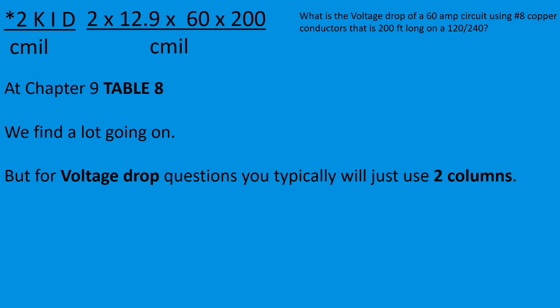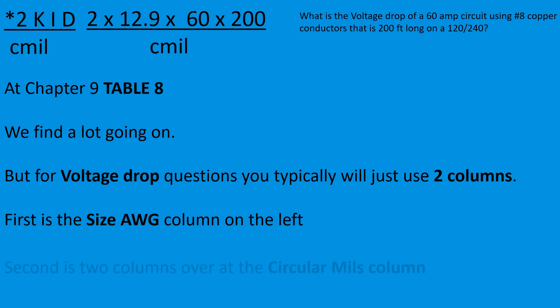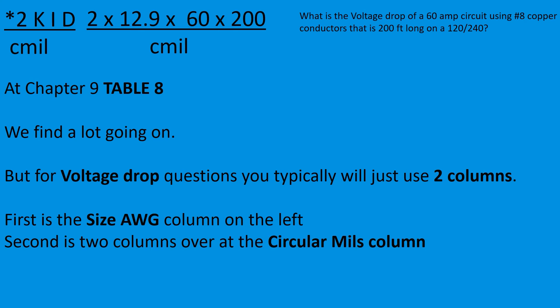For voltage drop questions you typically just use two different columns. The first one is the size AWG column on the left. That's going to be your size wire. So first select your size wire. We're using a number 8 copper. Second is two columns over, it's in the circular mils column. So go two columns over. Make sure you're in the cmils column. I want you to highlight both of these columns all the way down. So highlight the wire size, and then skip a column, skip over two columns, and you're going to use the circular mils column and highlight it all the way down.